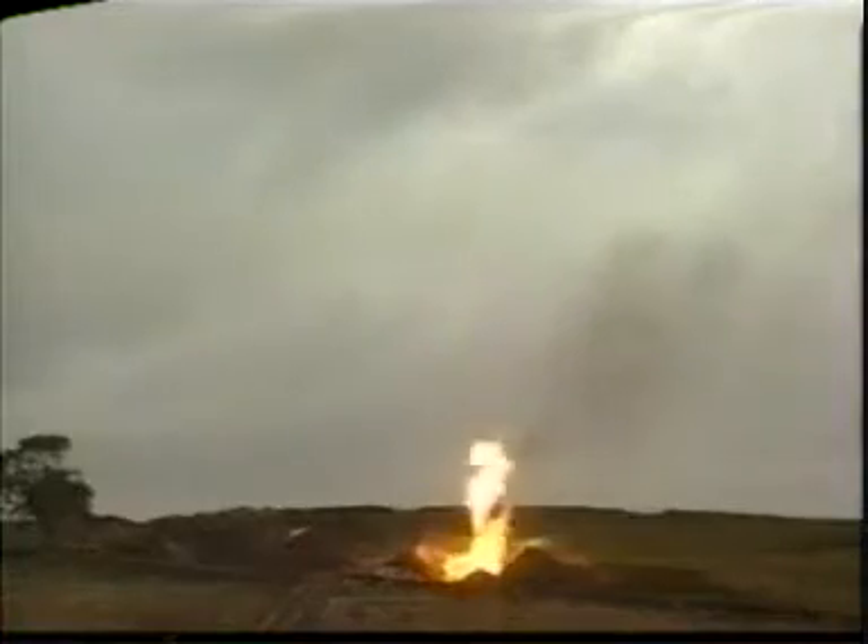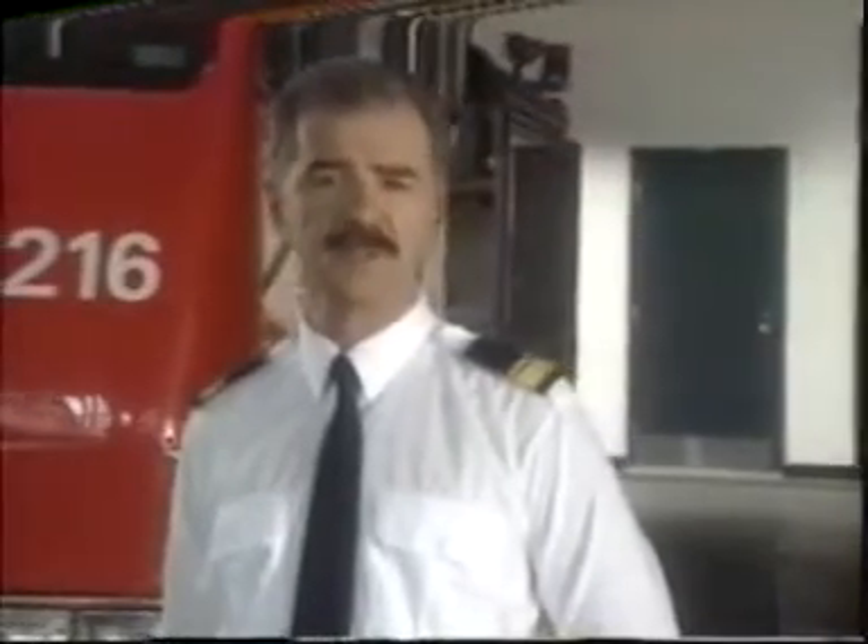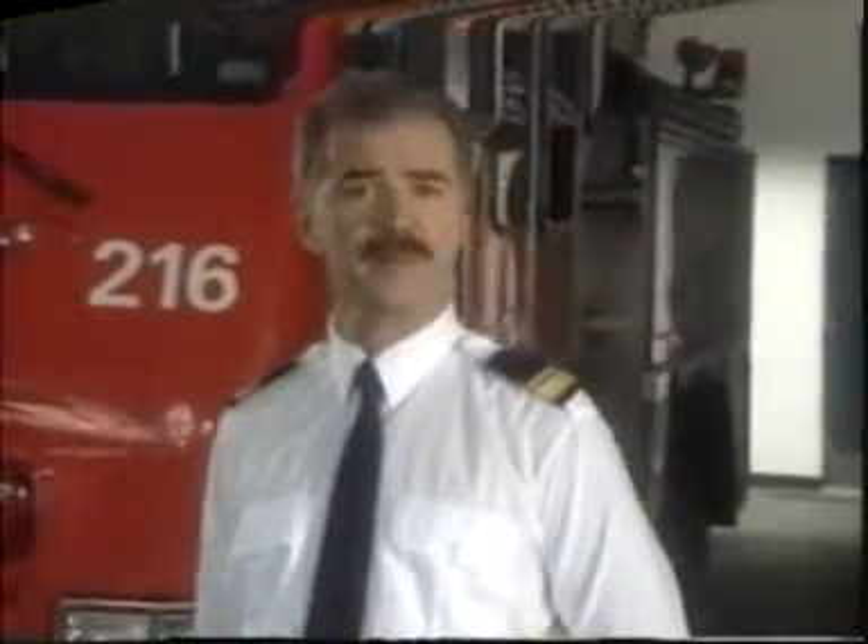Records show that in one severe case for a similar-sized tank, a projectile rocketed 22 times the fireball radius, about 400 meters. The best point for observation is beyond the minimum distance to avoid excessive radiation — face onto the side of the tank and with the wind at your back. Even here you can see that some fragments have fallen beyond the observation point.